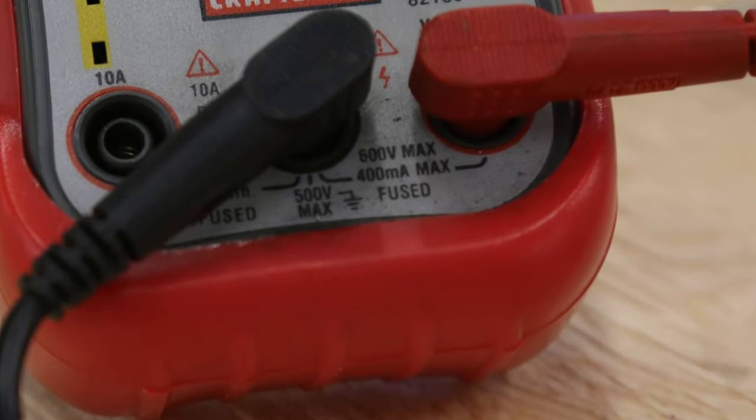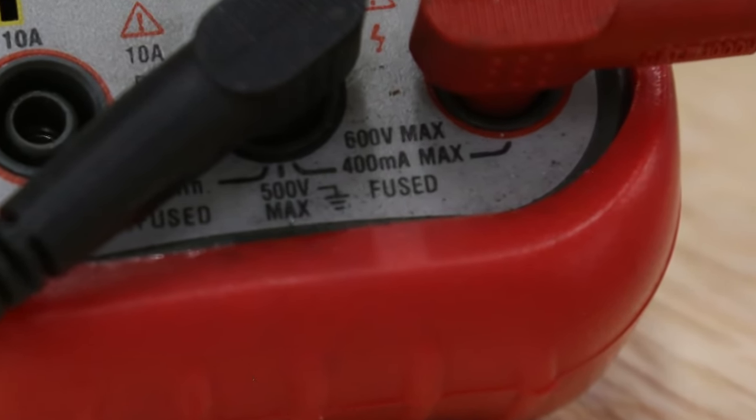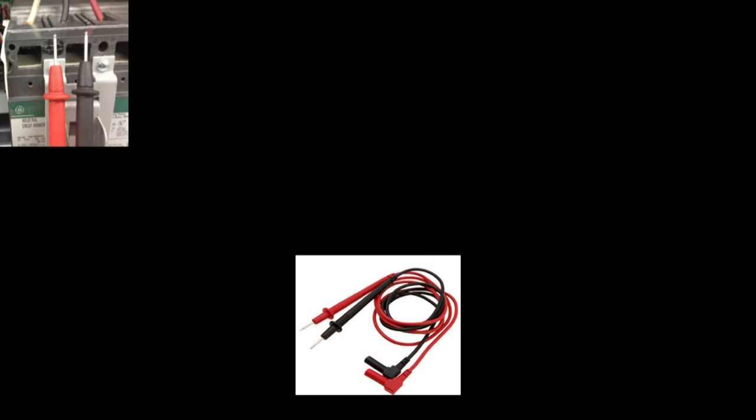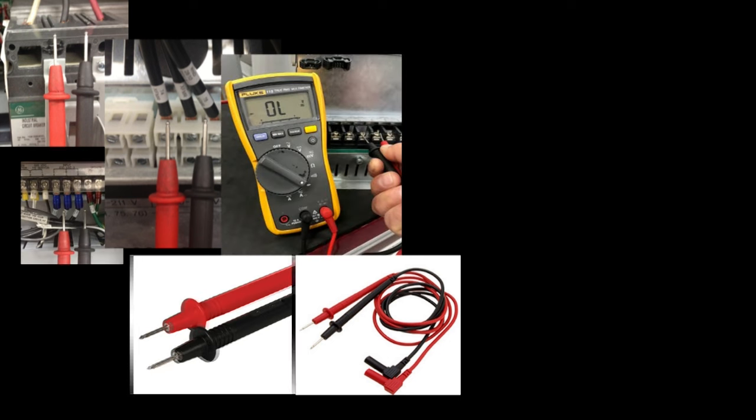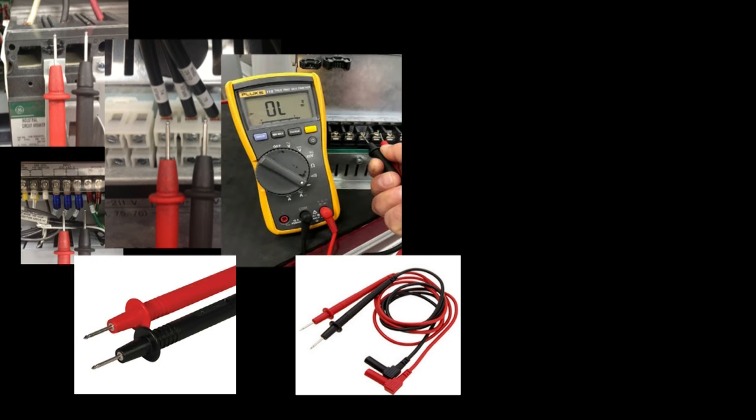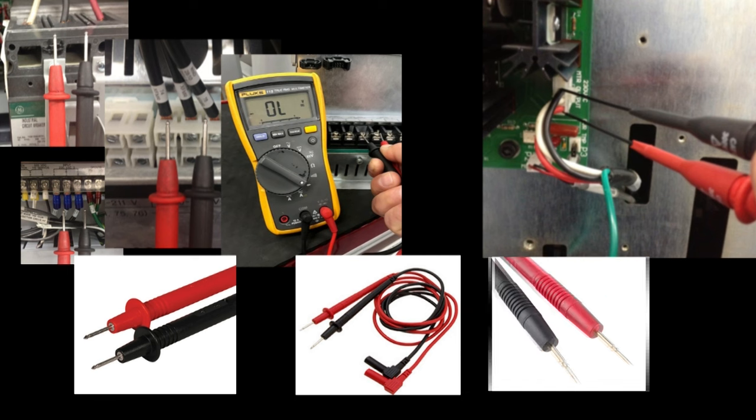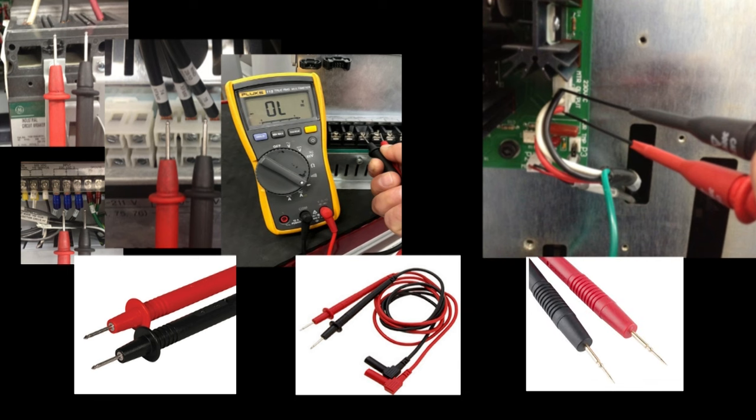Replace the battery in the multimeter the moment you get a low battery warning. Make sure the multimeter is rated to handle the voltage present in the circuit. The multimeter comes with different probes for different circumstances. If you're taking readings on terminal blocks, contactors, circuit breakers, or motor terminals, use the 2mm probes. If you're going to measure the back of a connector, use a needle probe. Don't use a 2mm probe. You might damage your connections.